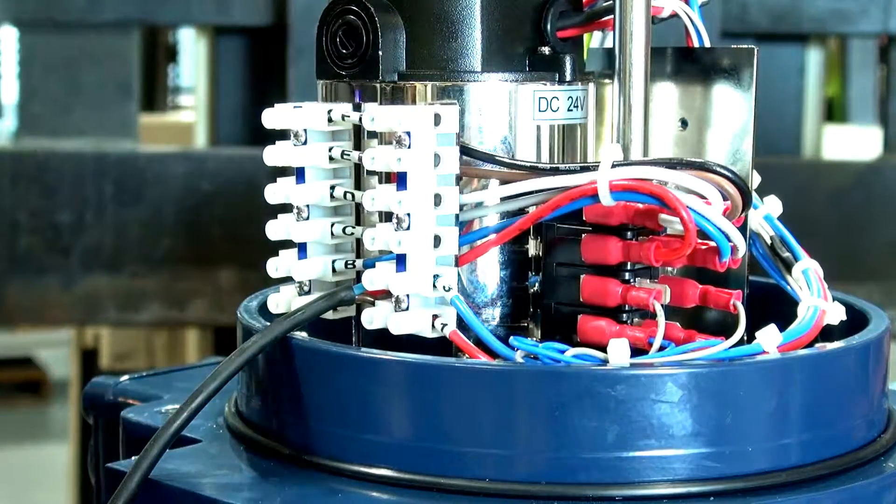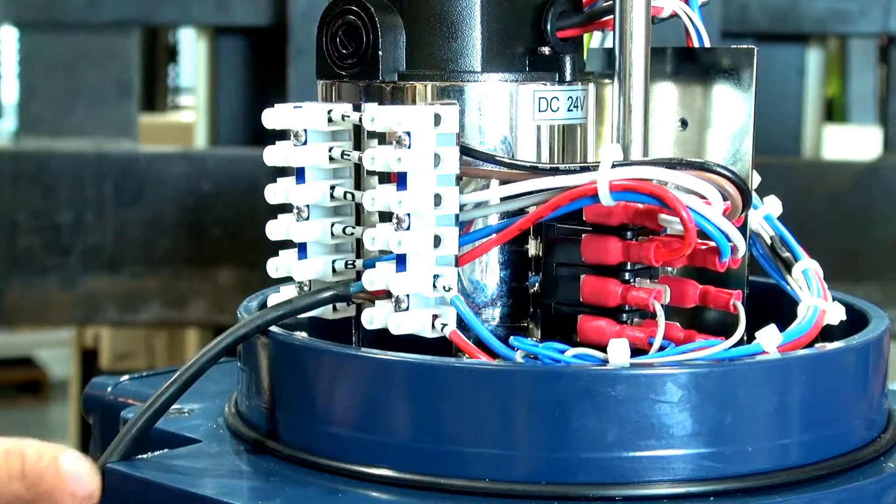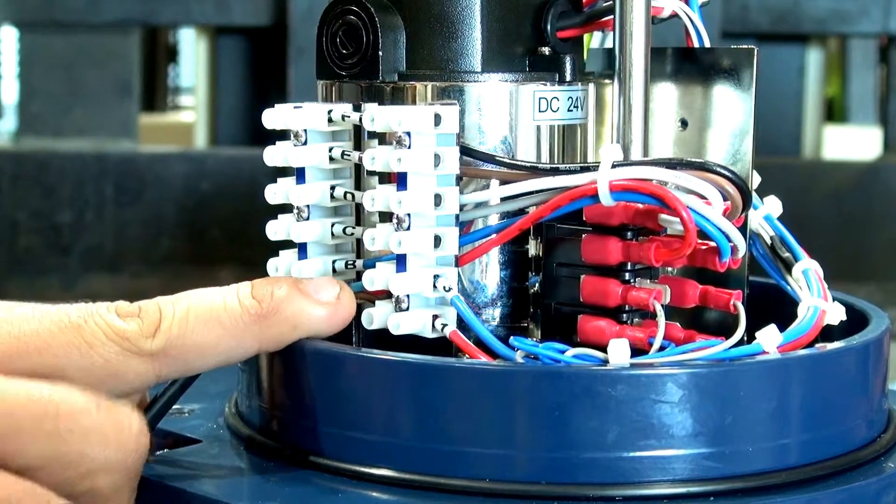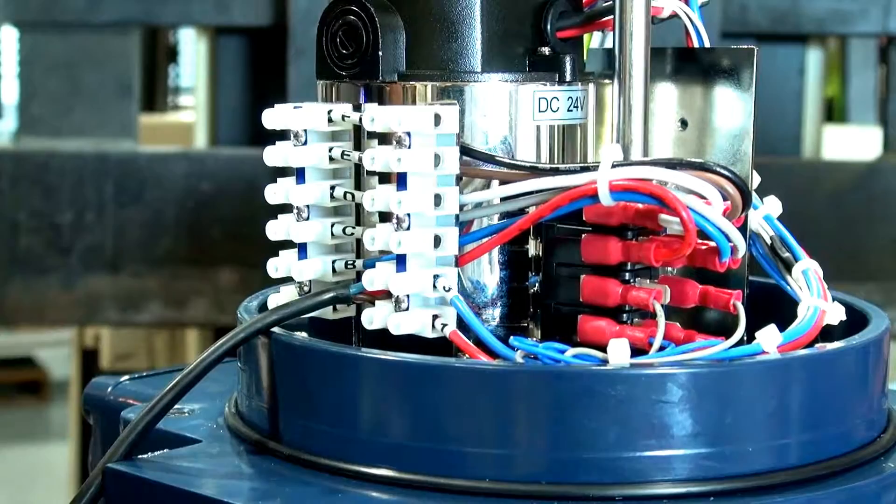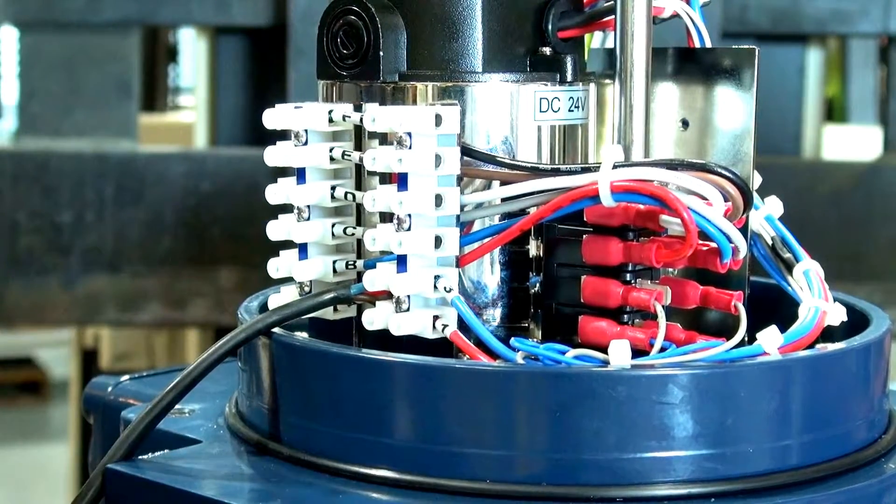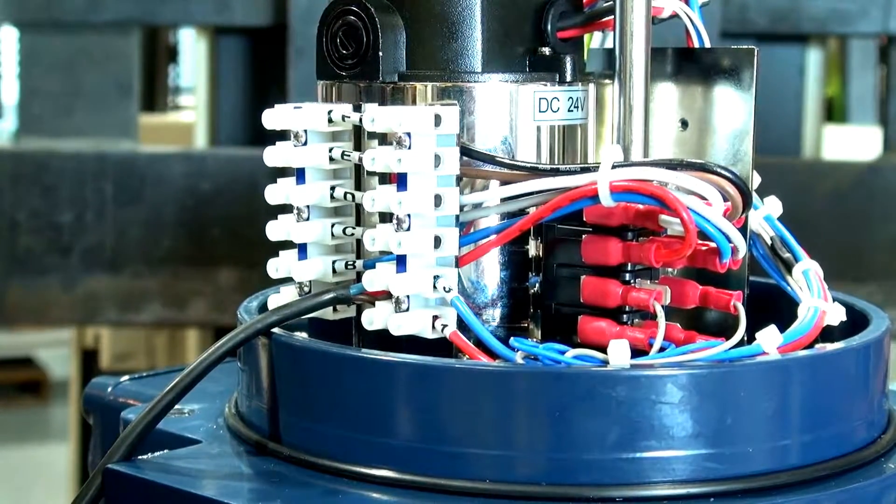This unit is a 24V DC unit and the wiring is pretty straightforward. We've got positive going into number one on the terminal block and negative going into three of the terminal block. As a spring return unit, it doesn't require power to close, so it just requires a switch to power it on and to operate the unit.